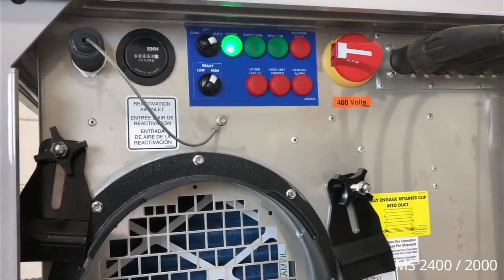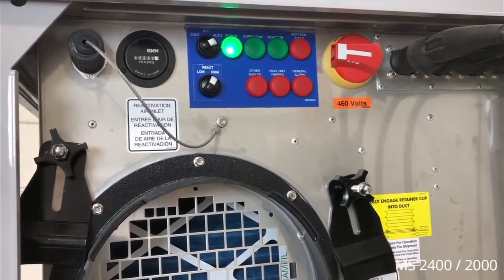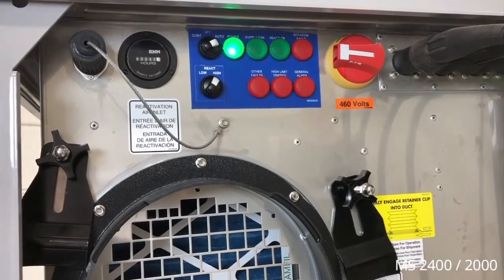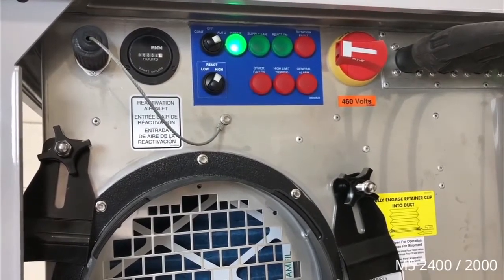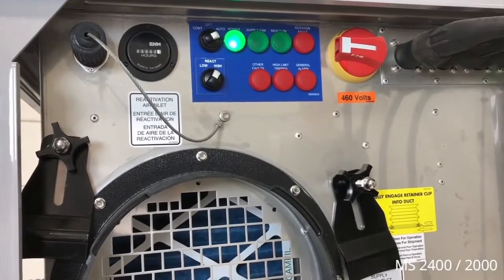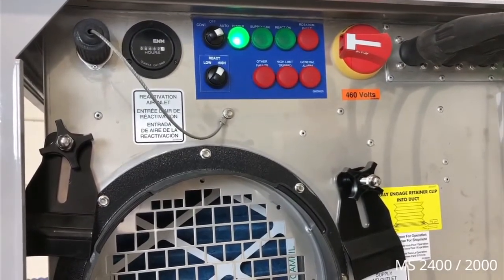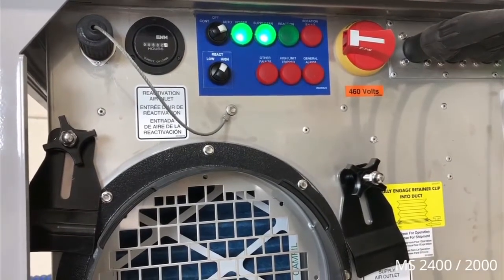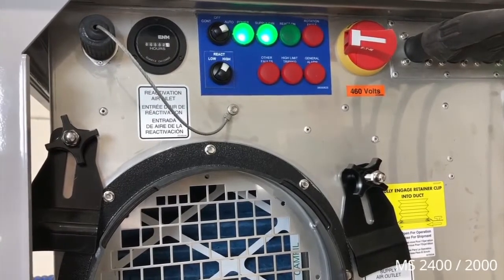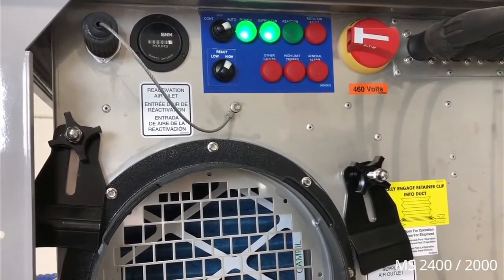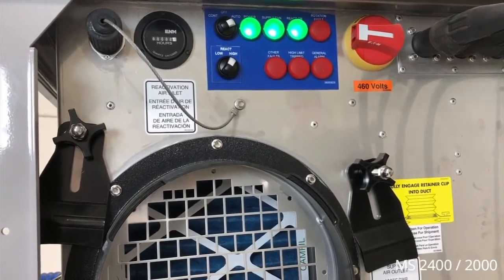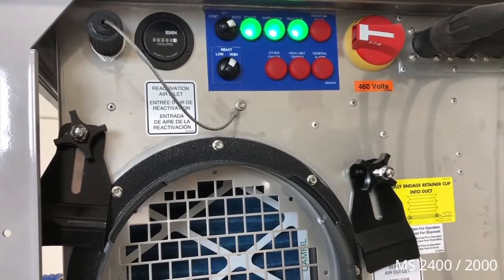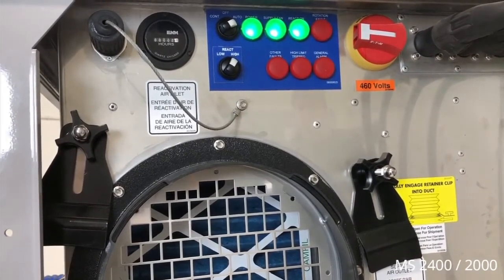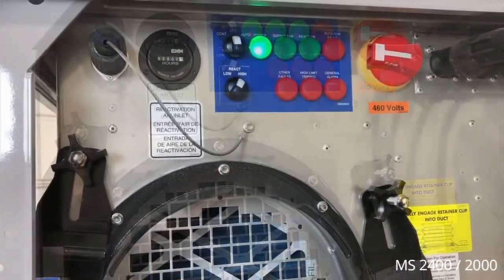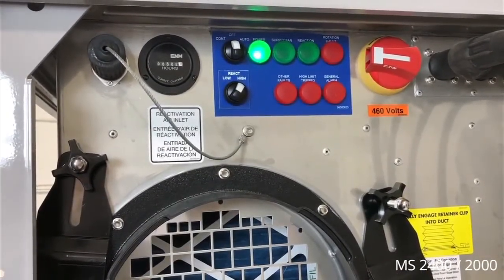Now we can start the unit by switching the unit to automatic. Again, the microprocessor is going through its self-check, and we're going to wait for it to make sure all the safety circuits are operational and ready to go. This will take about 30 seconds to 1 minute to prove the self-checks. Supply blower on. Reactivation fan on. And we are dehumidifying.